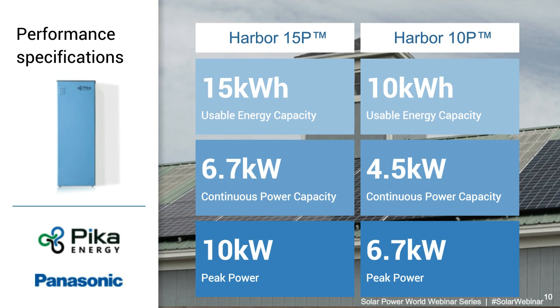And then the way that it installs on site is the Panasonic lithium modules ship as individual units. Each is 2.5 kilowatt hours in capacity. So if you put in 6 of them, you have a 15 kilowatt hour battery, and if you put in 4, you have a 10 kilowatt hour battery. And so when an installer purchases this system from a distributor, they can buy either the 10P and get 4 of the modules along with the enclosure and power electronics, or they can get the 15P and have 6 of those modules shipped with the enclosure and power electronics.